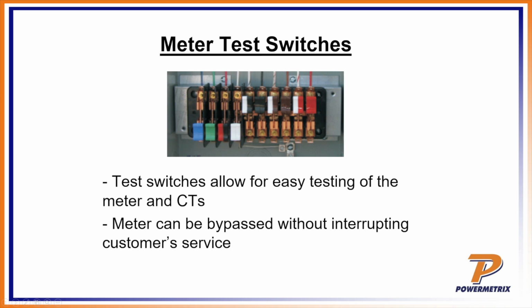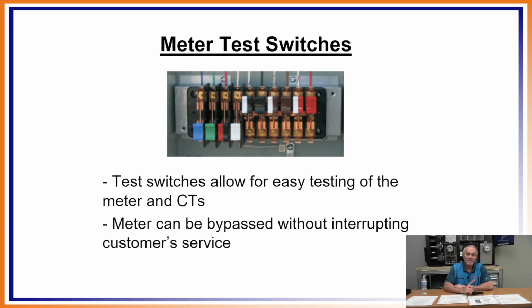So with those test switches, you can see there, they allow for easy testing of the meter and the CTs, and the meter can be bypassed without interrupting the customer's service. And that's a biggie, okay? When I throw those shunts on there, it just shunts across, but it doesn't disconnect anything. So I'm just reading. Remember, with our test equipment, we're going in just in series, okay? We're not interrupting anything. We're just inserting in there so we can still see that same flow of current going through there.